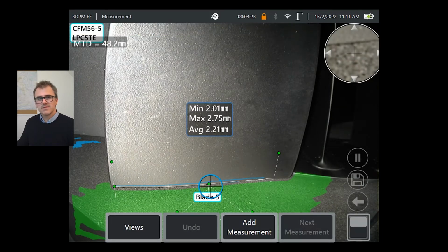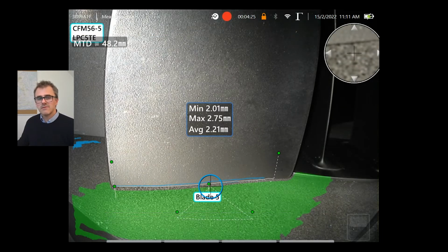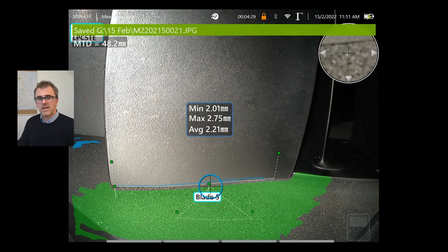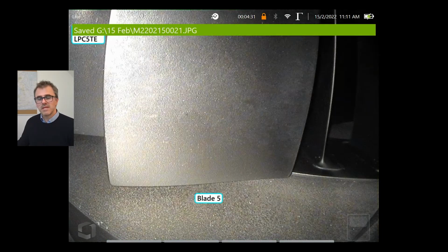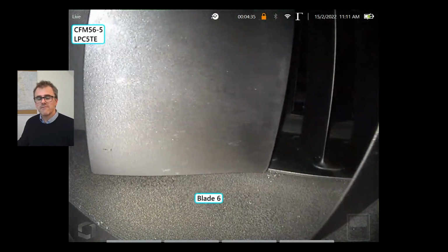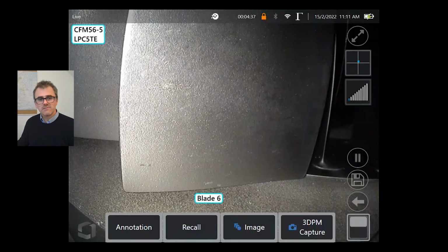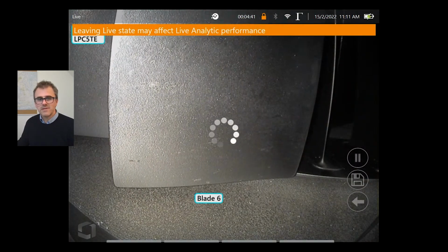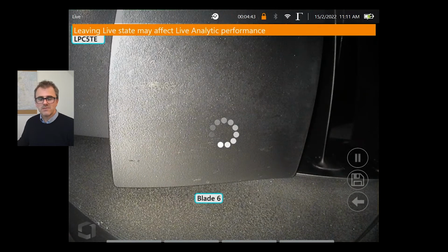So here we just see how quickly and how reliably it is possible to inspect and obtain such blade clearance measurement information, in this case associated with each aerofoil. And there's no need to relabel and update the text box. As we've discussed, we can just update, and it updates automatically using the blade counter analytic.